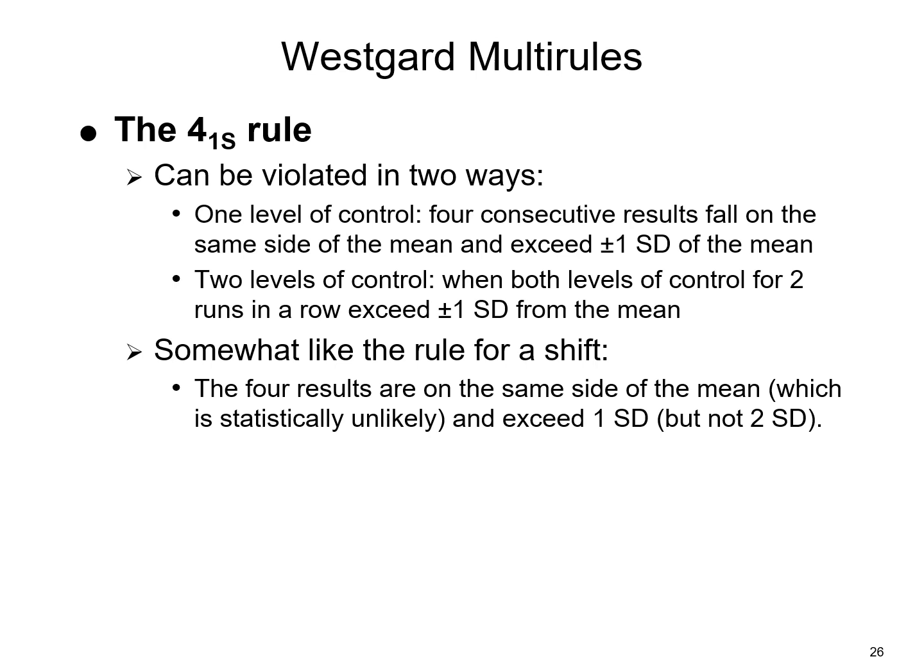Or it could mean between the 2 levels, the normal and abnormal, for 2 consecutive runs. So we've got to compare both data for 2 consecutive runs back to back to see if within both of those, the normal and the abnormal, we have 2 value points that have exceeded the 1 standard deviation to give us a total of 4.